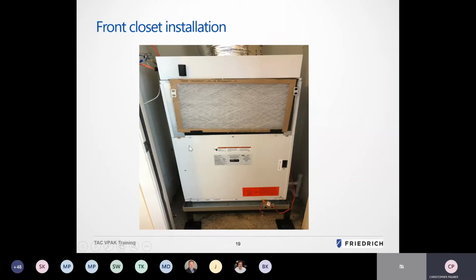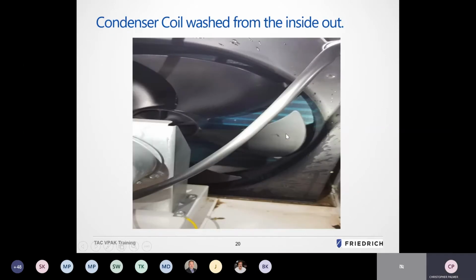And wiring comes in on the right-hand side. This is that same picture with the door removed. You can see here the drain line connection at the bottom with the support platform and your air filter in place. This is a VHA 18 model. With the door panel removed, oftentimes you're able to access the inside of the blower compartment or the condenser section. The condenser coil can be washed carefully, without damaging the plastic, from inside to out, without removing the unit from the closet. That's something that's often challenging with limited closet access. But in this particular installation with the front access, you can get to that coil, that condenser fan motor and wheel, and all of the other components in that lower compartment, as seen in this close-up image.